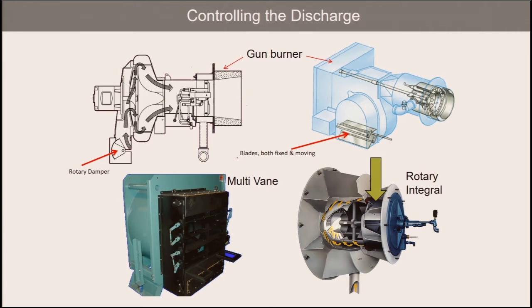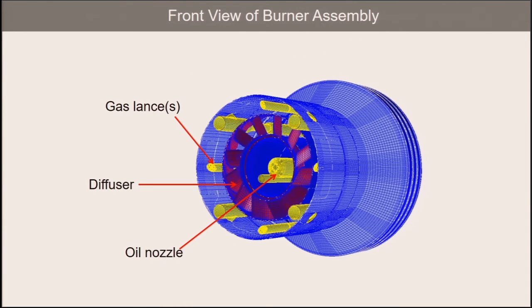All of the air regulators described so far have inlet dampers, meaning the air is being pulled through them by the centrifugal fan. In the case of the damper in the lower right, this is a discharge damper — the air comes in from the top as indicated by the large green arrow — and the rotary sleeve within the housing has contoured openings. As it rotates through a single drive mechanism, it regulates the air based on the required firing rate. You'll find this type of dampening system in burners using an integral front head, where the burner is mounted within its own combustion air wind box.